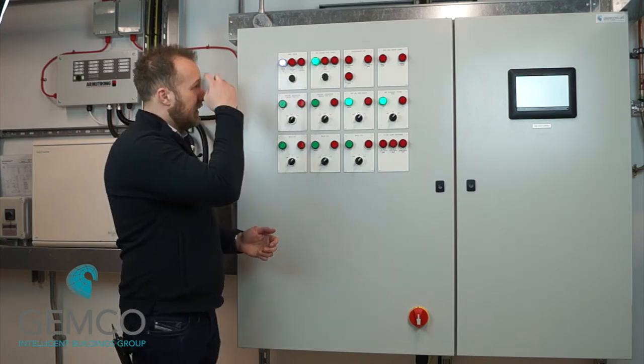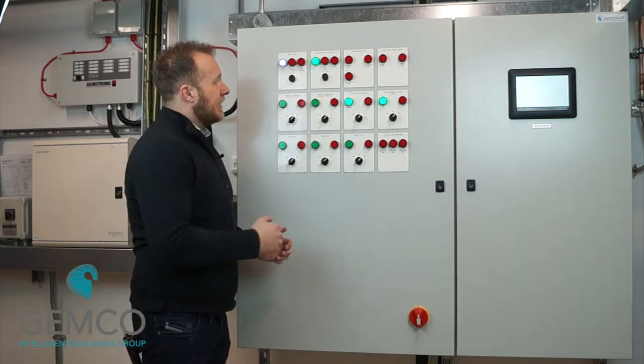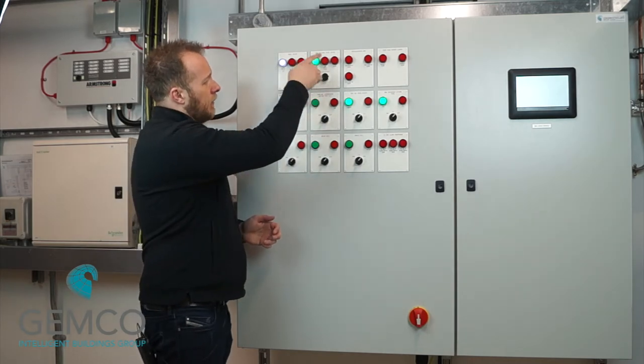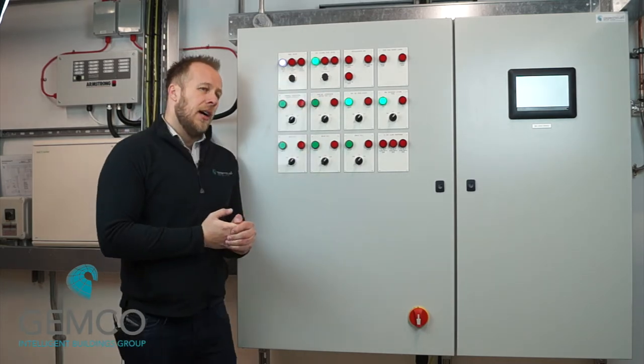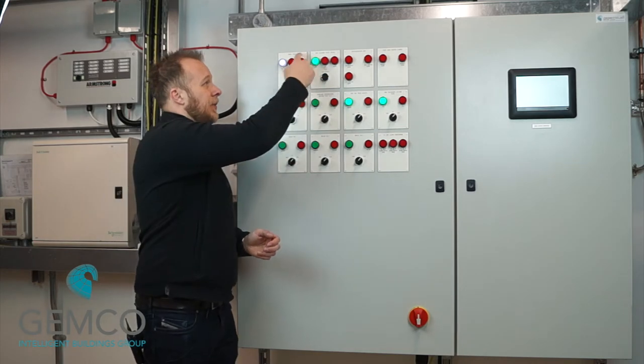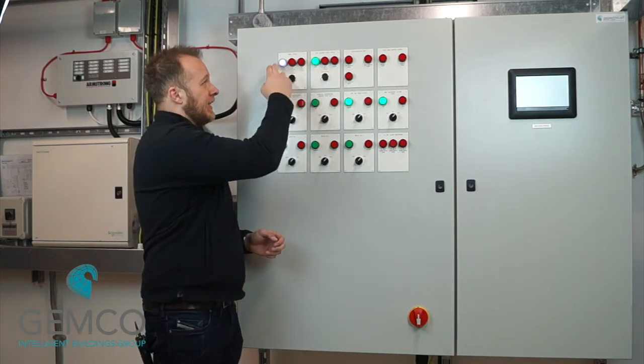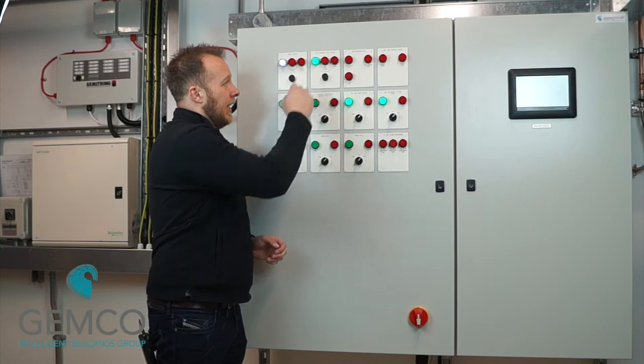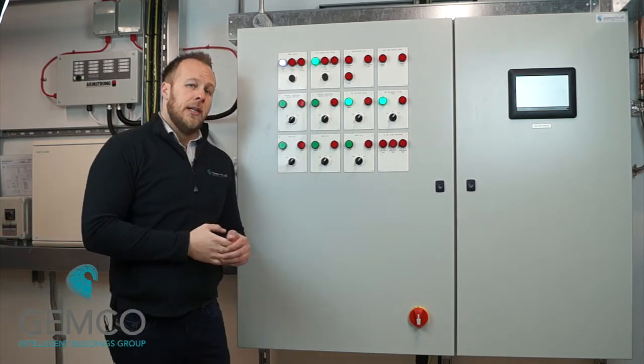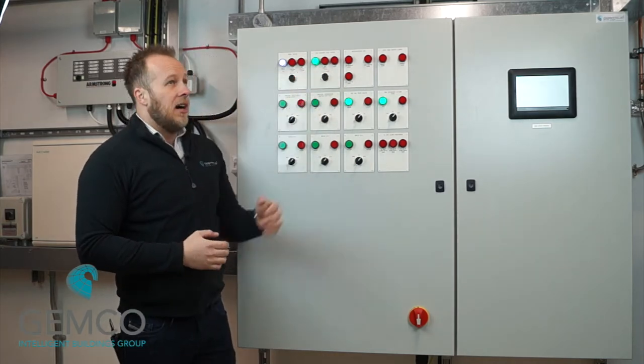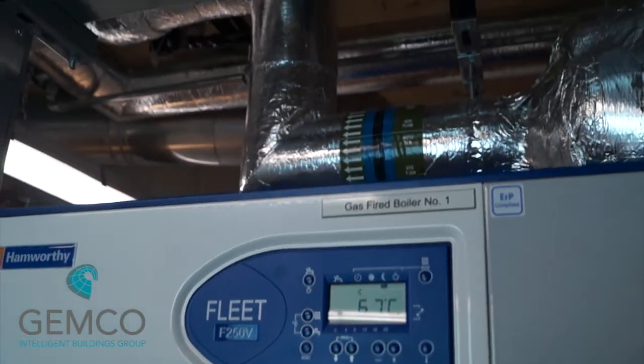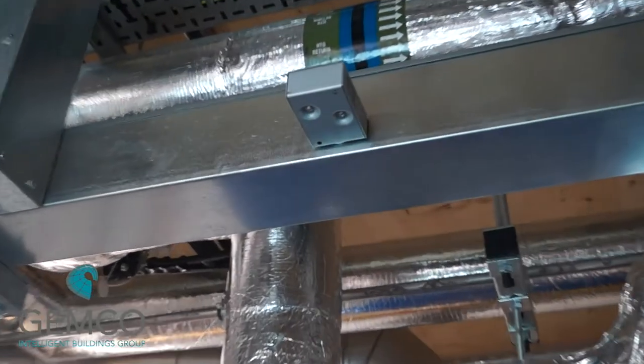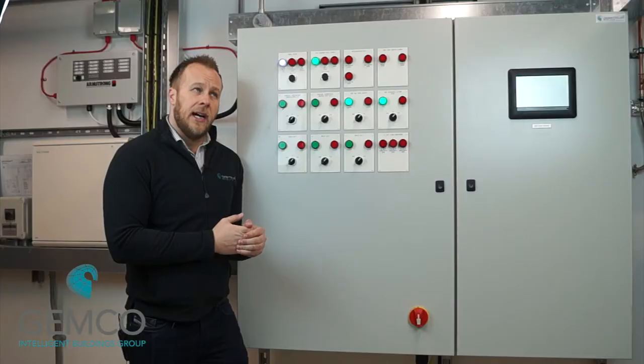Now we're going to move on to the gas. These are all the life safety systems. We're going to move on to the gas solenoid valve, which will relate to these safety systems, because if any of these safety systems are ruptured, then the gas valve will close. Now on top of that, there's a thermal link above the boiler, which is a small little piece of lead, and that will break when it gets too hot.